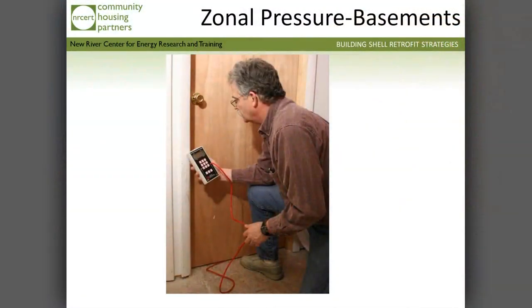That's a good point you brought up, because has anybody run across a door that's perfectly weather stripped but the door is crooked or warped? Sometimes you can do a zonal to the garage or the basement and think, wow, that basement or garage is really connected to the interior space. But you could just push on the door and realign it to the weather stripping, and you watch that zonal number go up. It's like, here's most of my problem right here. So that verifies that it's mostly the door.